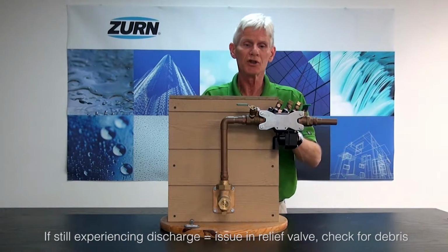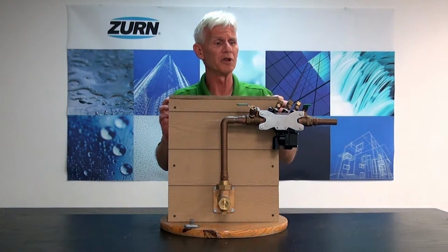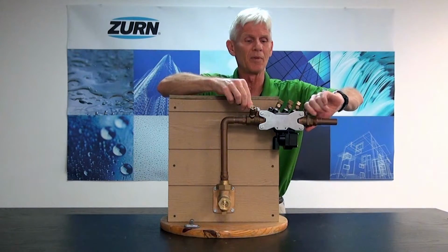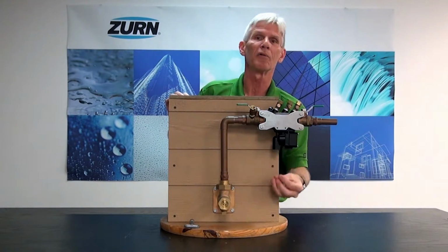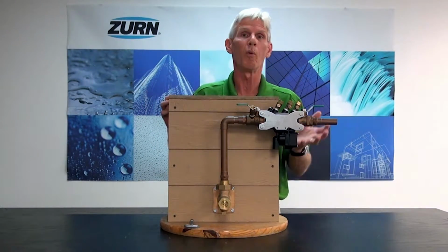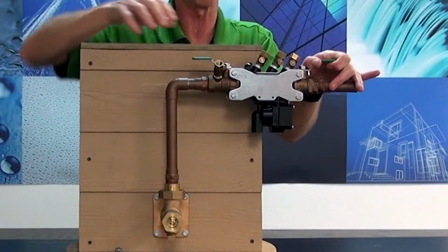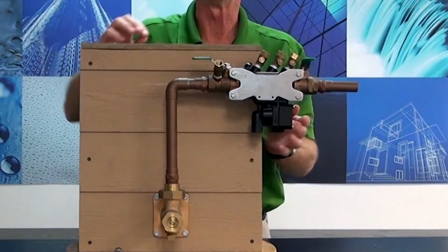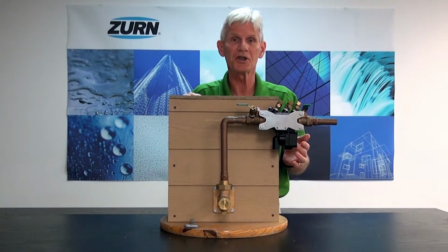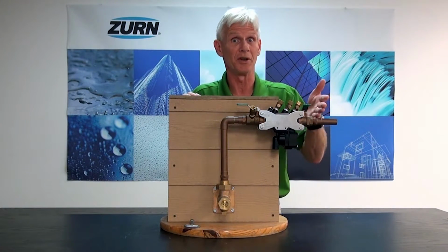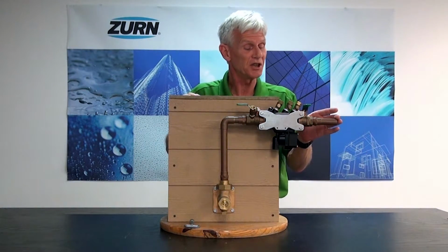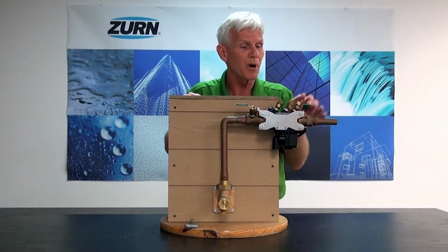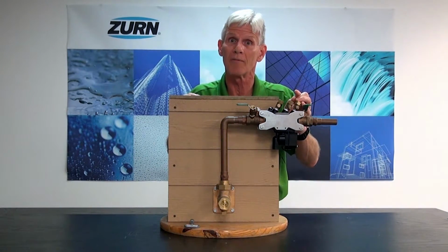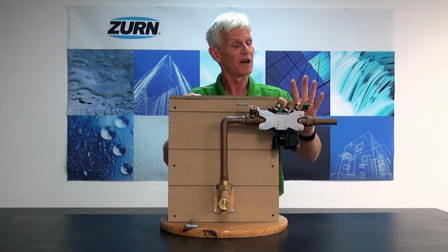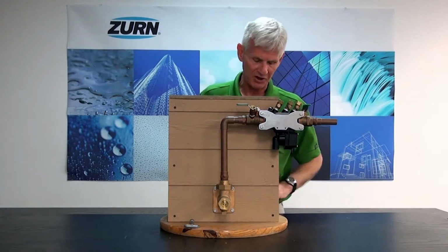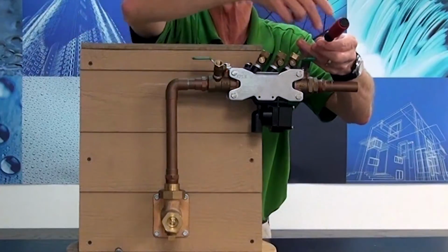So I think I'll just, for the sake of argument, go through these procedures again, just to make it clear. We walk up to the backflow preventer, we have relief valve discharge coming out. What we want to do first is shut off the outgoing ball valve. If I see the discharge ceasing, I know that I'm under back pressure and I have a leaking number 2 shutoff or check valve. Next, if I see no change, I want to open up test cock number 4 and induce a flow through the assembly.